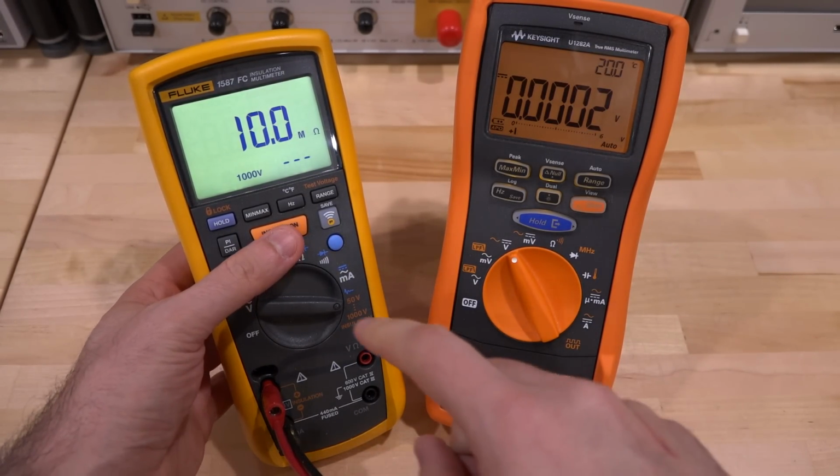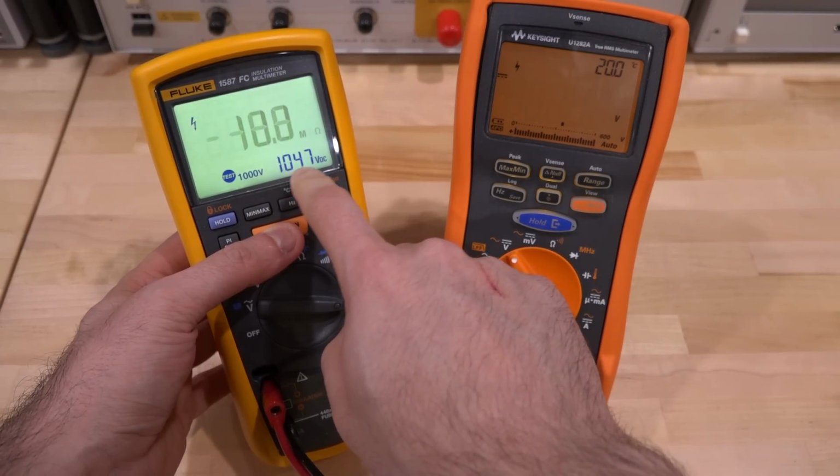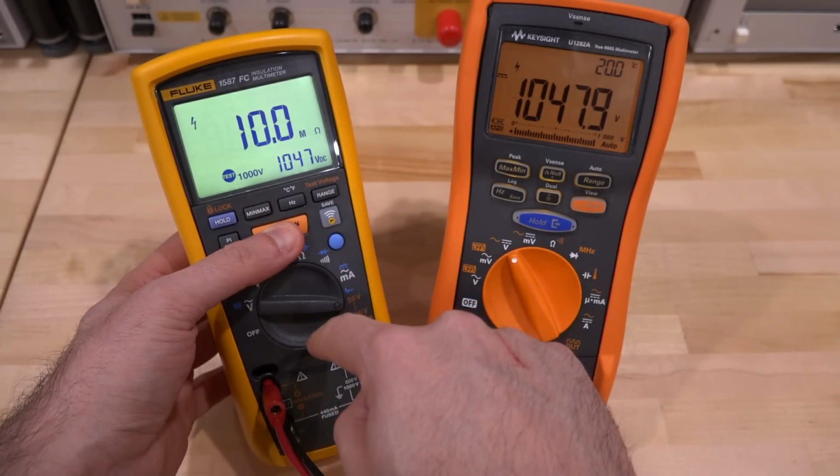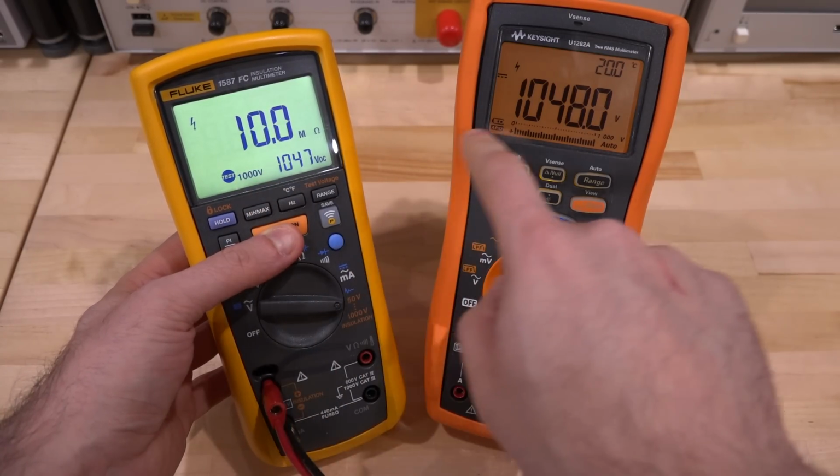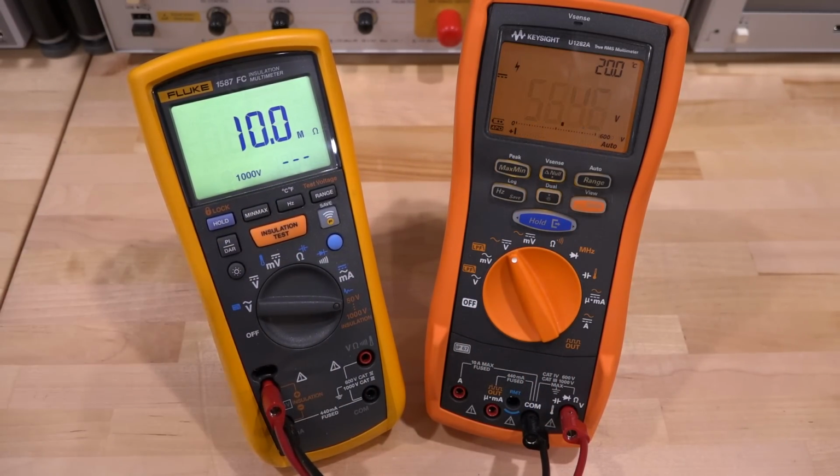But this is an interesting example because it's clearly measuring the internal voltage and using that with the internal current to tell you what the resistance is. But it's not applying 1,000 volts at all, it's applying anything that's close. So an interesting example of a not so accurate high voltage power supply used for precision measurement.